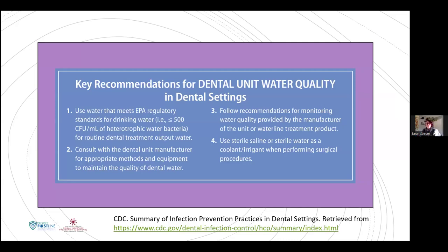All right, our next domain is dental unit water quality. And this is really one that's specific to dentistry and not really translated to other healthcare settings. So the CDC says that the water we use for dental treatment should meet the EPA standards for drinking water, which is less than 500 colony-forming units per milliliter of heterotrophic water bacteria. And that standard is pretty general.